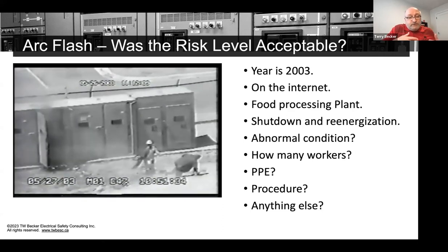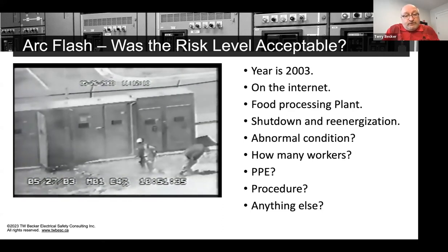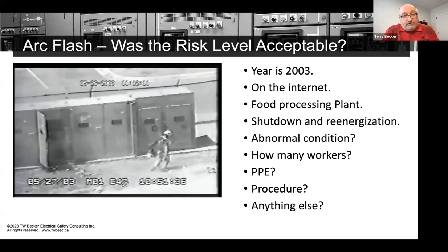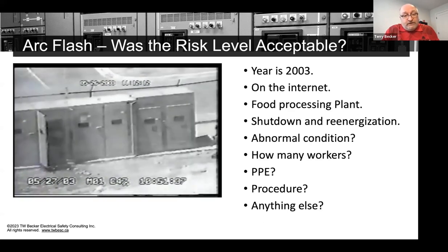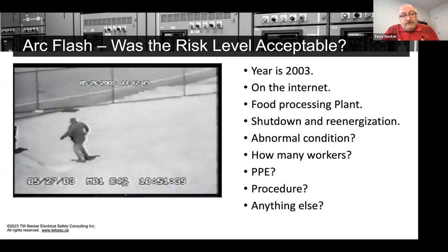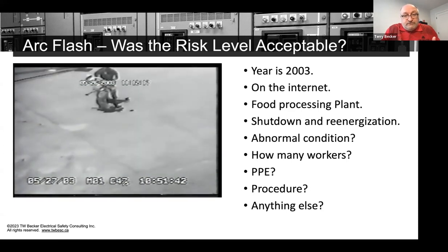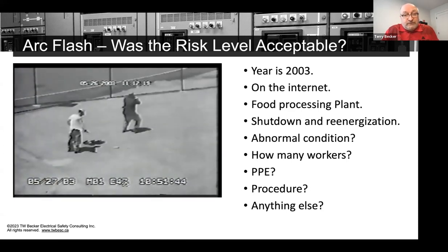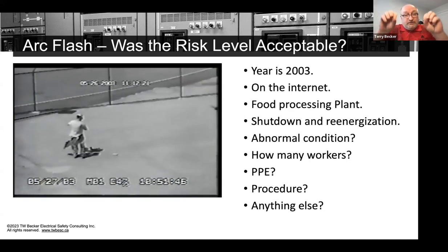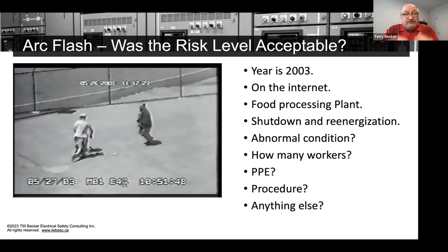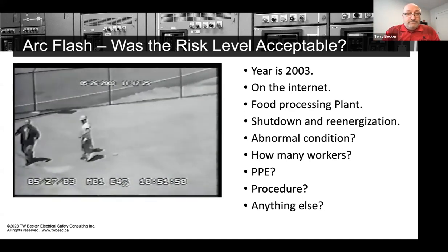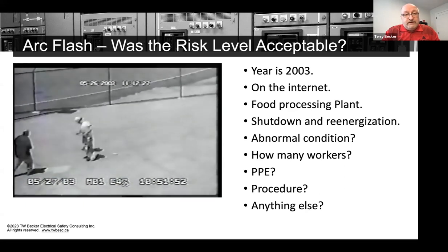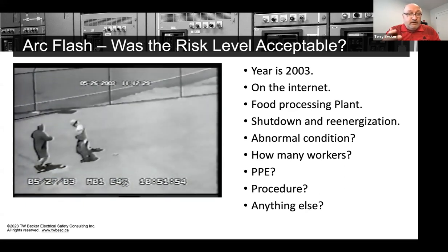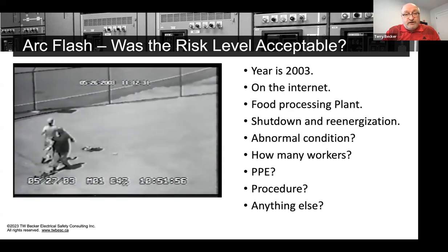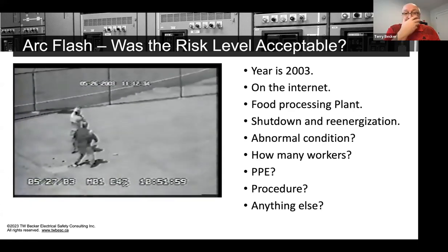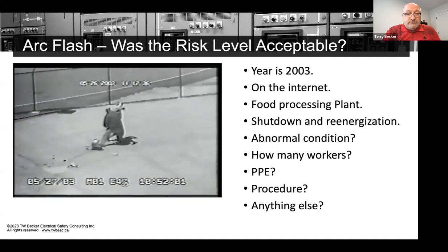The one gentleman came towards me, his clothing on fire. The gentleman with the hard hat still on, his clothing is on fire. They're both in traumatic shock. The camera pans, and the gentleman in the darker shirt, whose clothing's not on fire, starts to come out of traumatic shock, but he's still in shock because he starts to rip off the burning clothing and burns his hands probably, doing that. So, second, third degree burns. They had hair nets on that were not arc rated at the time because they didn't exist, because it's a food processing plant. You can now get arc rated beard nets and hair nets for industries that require it.